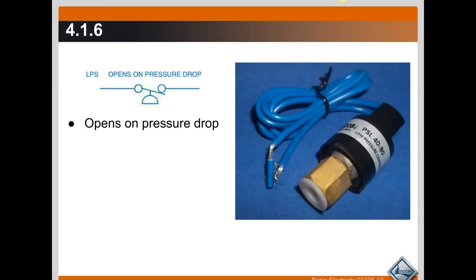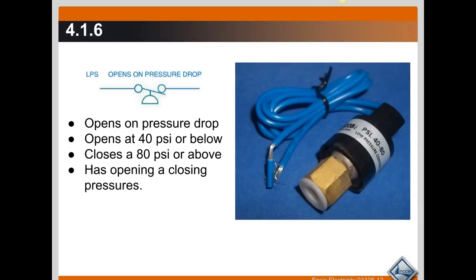This switch opens on a pressure drop. It opens at 40 psi or below, so at 40 psi, 39, 38, this switch is open. And it closes at 80 psi or above. Unlike the temperature switches we looked at, those have an opening or closing pressure and then a range.